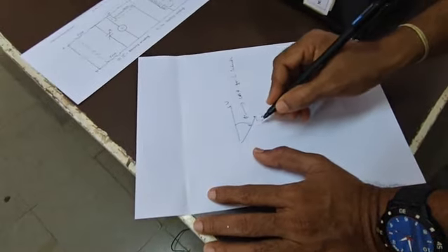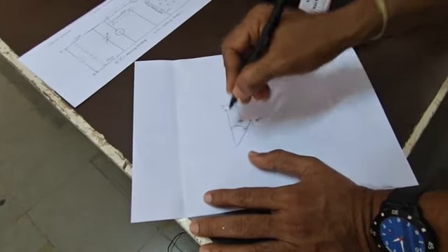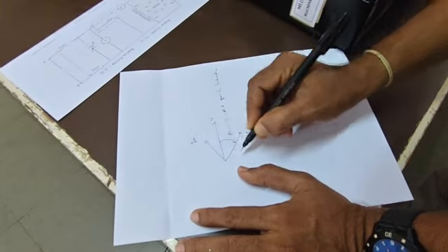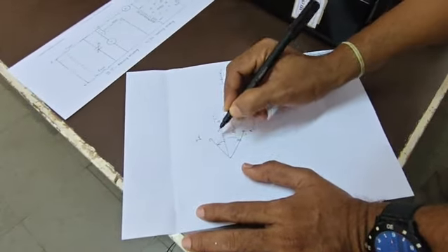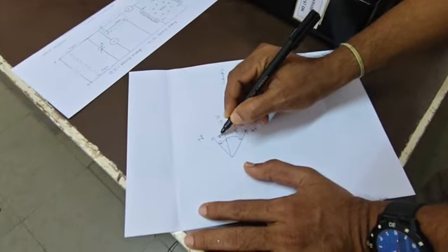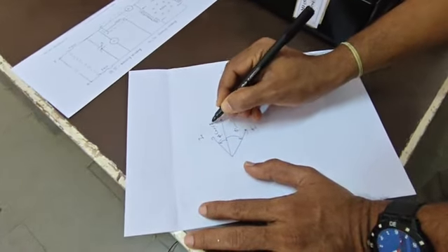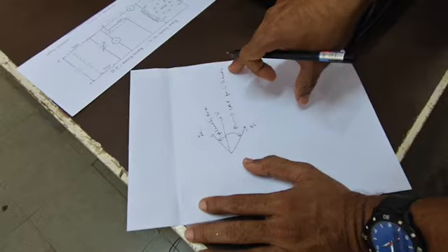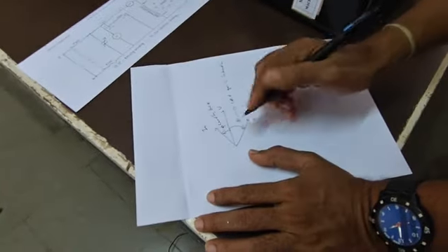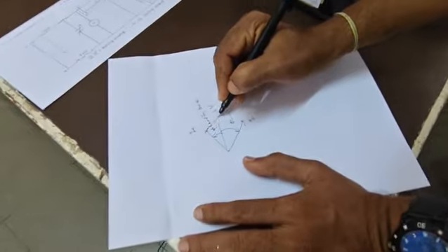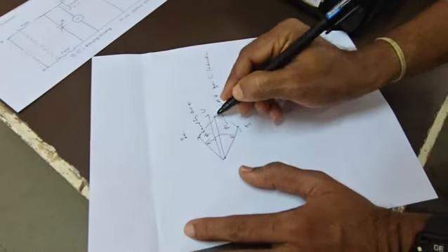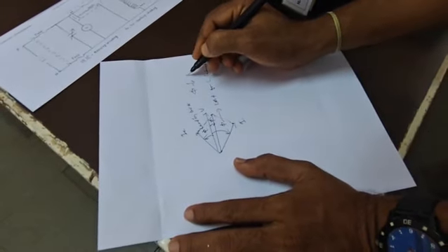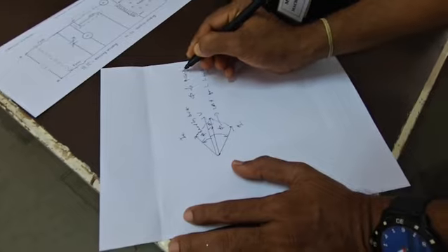Now when I want to improve this power factor, that means when I want to decrease this power factor angle, I need to add a capacitive load where it draws capacitive current. That means it provides leading kVAR. So with an inductive load, if I add a capacitive load, then I am going to get the resultant current as shown here. That means phi angle decreases, which implies power factor increases.